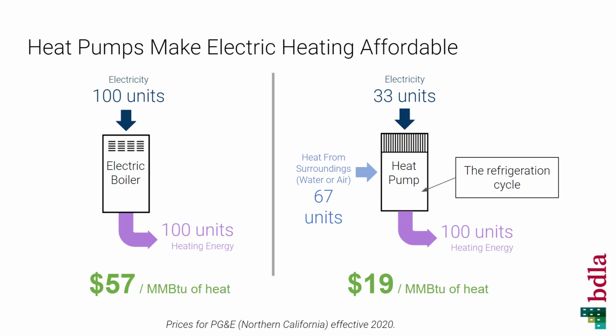Now when we compare the cost metrics of a heat pump to an electric boiler, because the heat pump only needs a third as much electricity as the boiler, the cost, of course, is much lower. So now we're down to only $19 per MMBTU of heat, as compared to $57 for the electric boiler. And as a reminder, the gas boiler was $18, so the price is very comparable. In the coming years, we're expecting gas prices to increase, and likely very soon the heat pump will actually be less expensive to operate.